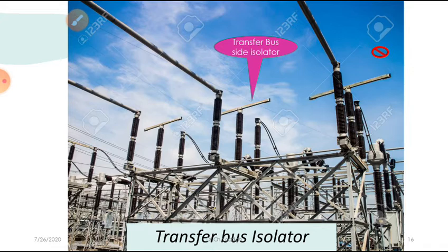So while operating any isolator, you should remember that you have to be very careful. You have to ensure that the circuit breaker is opened. After that you have to operate. This thing you have to remember. Now what are the applications of this thing?